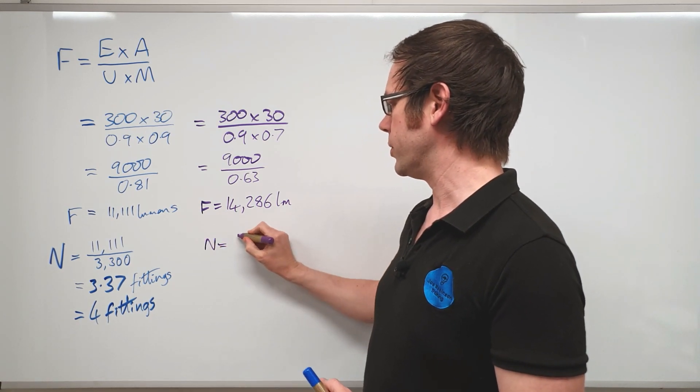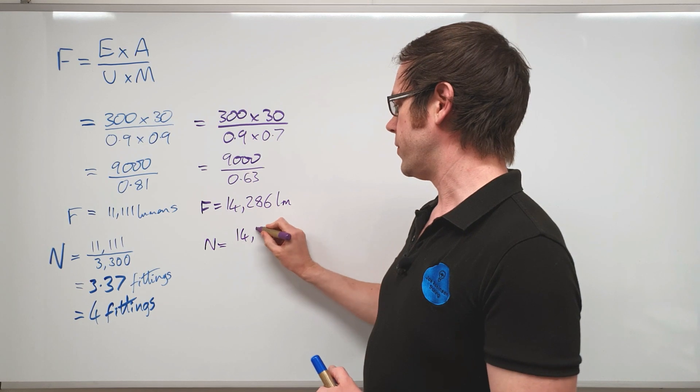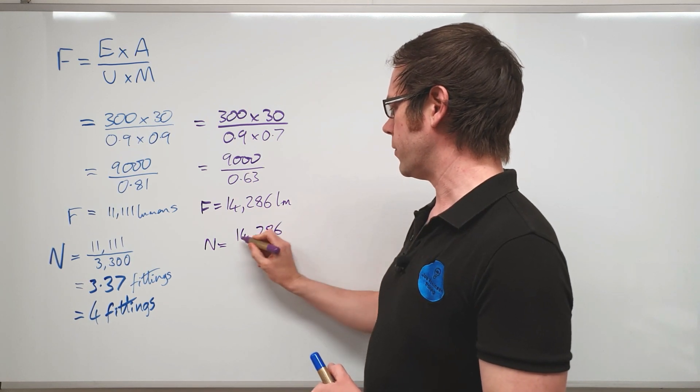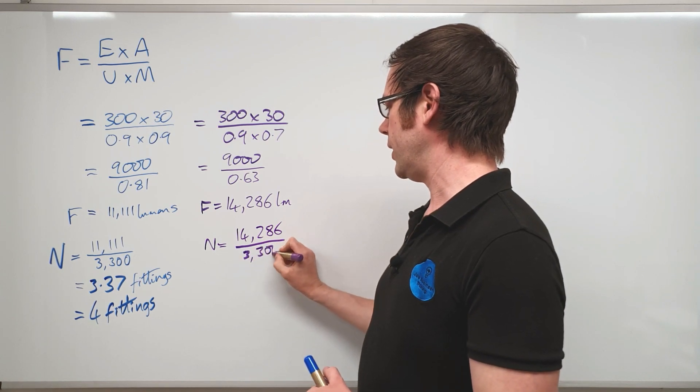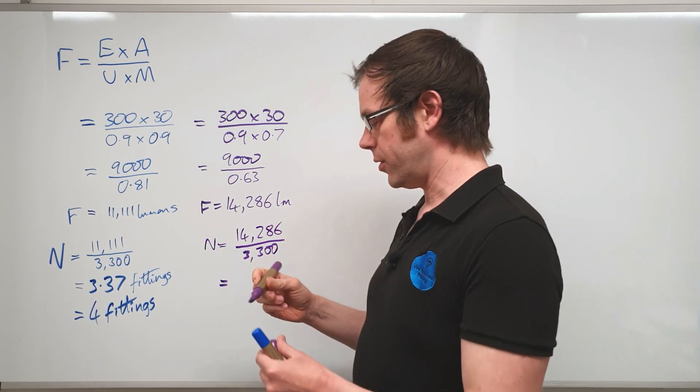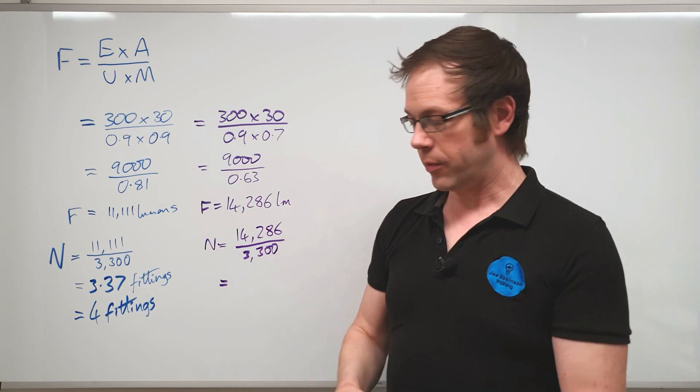So let's apply the same principle to this value of luminous flux and say that the number of fittings will be equal to the luminous flux that's required to illuminate the space, so 14,286, divided again by that value of 3,300.